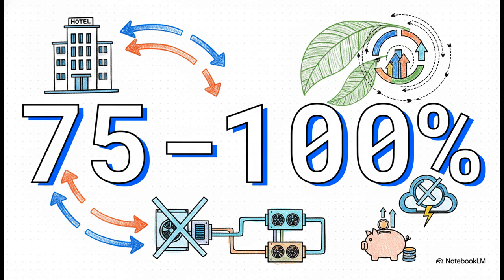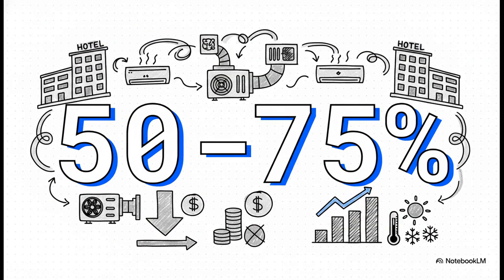I really want to let that sink in. By simply changing the architecture of how your building's climate is managed and utilizing simultaneous cooling and hot water production, you are effectively wiping out up to 100% of the wasted energy typically seen in standard VRF and air handling unit combinations. Furthermore, because the system balances these internal loads so efficiently, you can actively reduce your installed peak power by 50 to 75%.